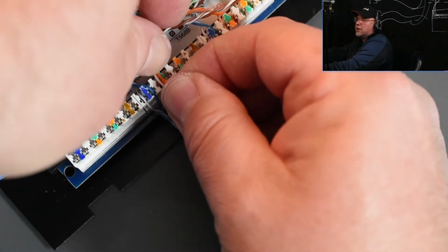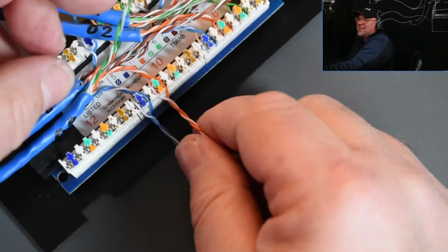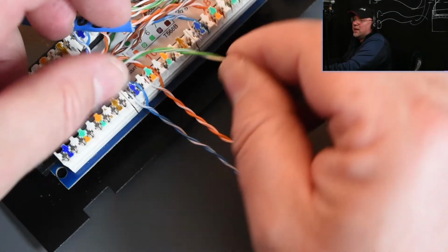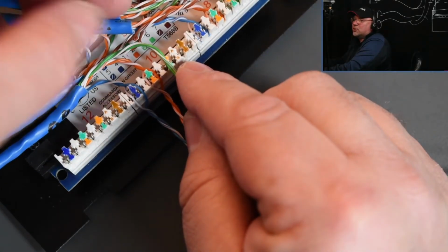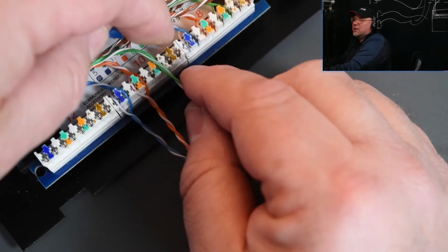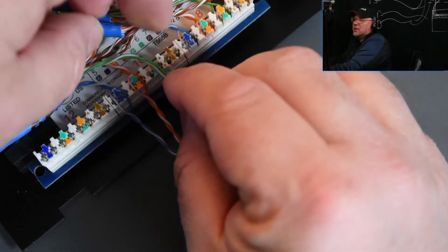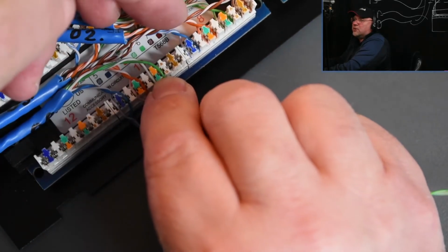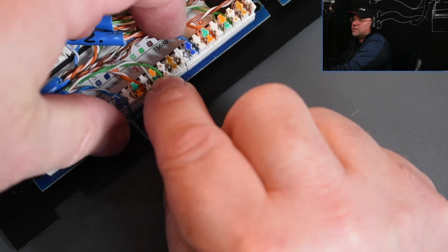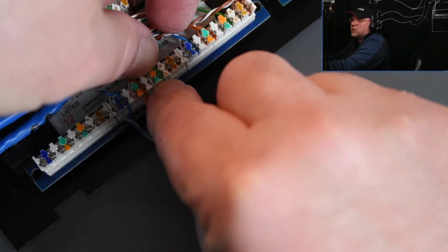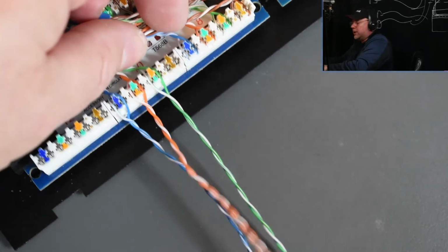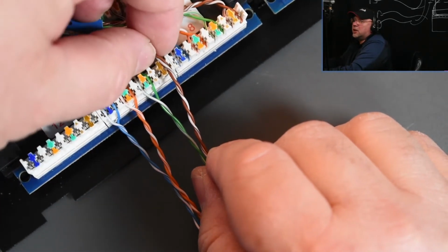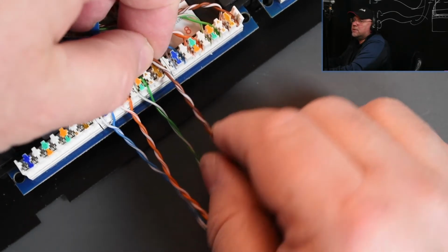I'm looking at the camera here. All right. And here is, see, don't try to make it like that. Do it like this, so there's no strain on those. Now here, you can gently do it. That's okay, that's fine. The twist is still far enough here, right to the punch. We don't want to lose twist. You lose twist, you lose bandwidth, basically. You lose the specs.